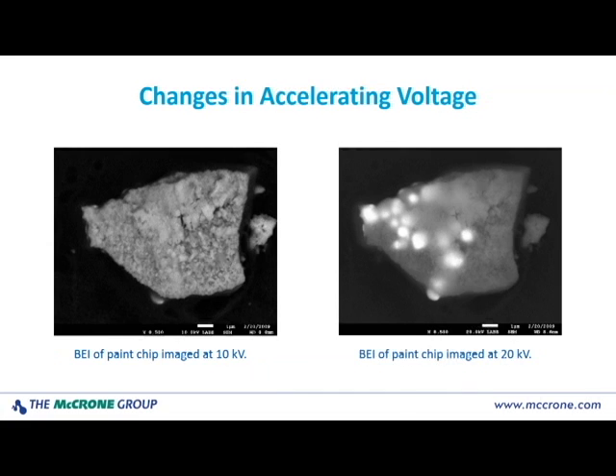If you were doing elemental analysis on these, you're going to want to examine the different brightness contrast levels to make sure exactly what's going on. Because in your backscattered image in compositional mode, the actual brightness contrast is determined by two factors: one, the composition at any given point — an average of all the elements at that point — or the topography or surface structure of the sample. So you can actually have black holes in the surface of this sample where there's just no material there. If we go over to the right on the same paint chip and boost the accelerating voltage to 20 kV, we have these bright features showing up — lead particles associated with our paint chip. They're not on the surface because we couldn't see them at the lower kVs, so they are subsurface or embedded within. In the secondary image, there was no indication they were even present. So you need different conditions — use your different detectors.